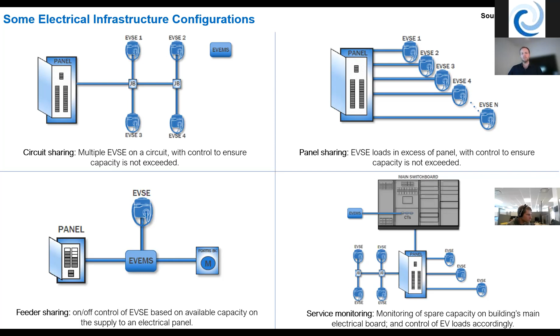Now, one thing that's interesting is that in new construction, the electrical code is inherently conservative. So for so many of these multifamily buildings, the very highest loading over the course of a whole year that the building's main transformer and service might have could only be about 30% of its actual nominal capacity. So there's all this additional capacity that you're able to use to provide EV charging within the existing capacity of those buildings as they would be designed without any EV charging infrastructure. So hopefully that makes a bit of sense. We can return to that a little later on in my presentation.